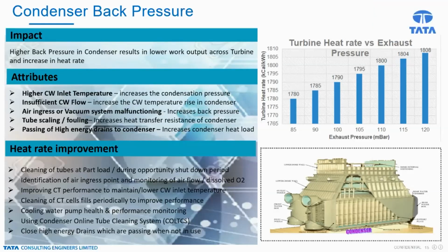Here we have tried to assess how increasing the condenser pressure impacts the turbine cycle heat rate. Typically we have done this for an 800 megawatt unit. If we see the base case for 100 millibar, the TG cycle heat rate is 1790. As it increases from 100 to 105, the TG cycle heat rate also increases from 1790 to 1795, then subsequently for 110, 1800. So in this sequence, as the condenser pressure is increasing, the TG cycle heat rate is also increasing.